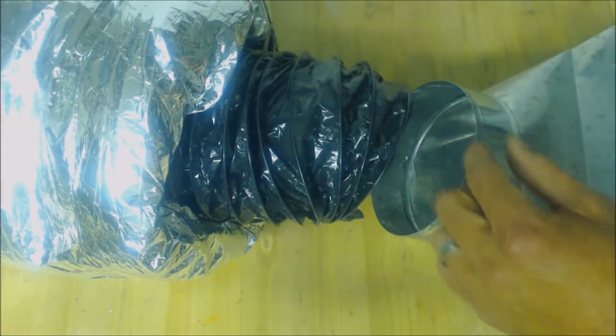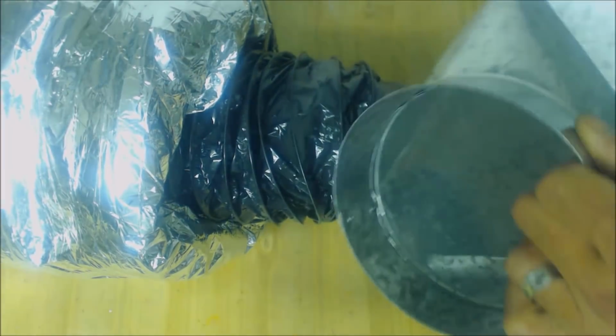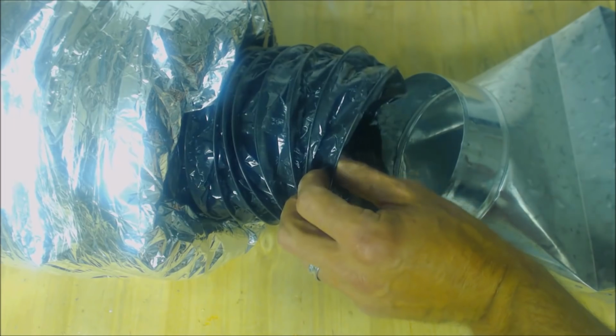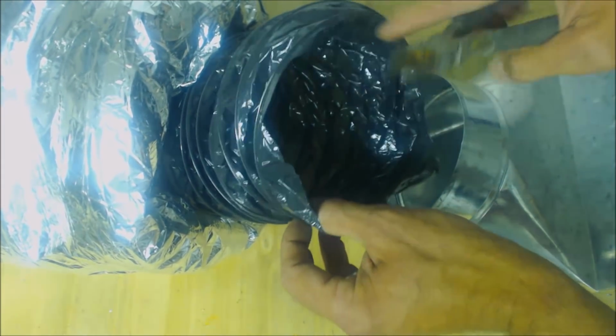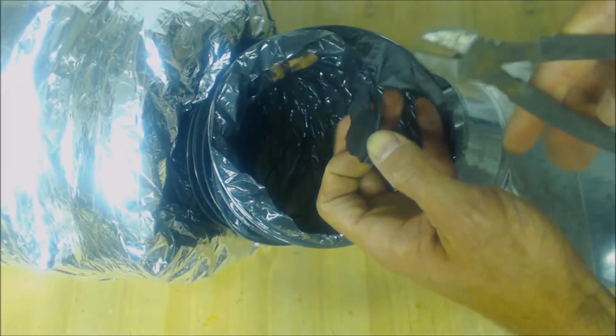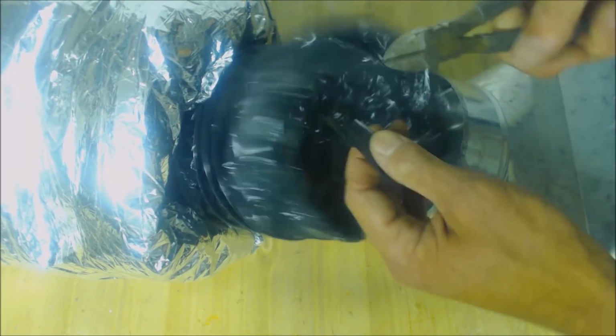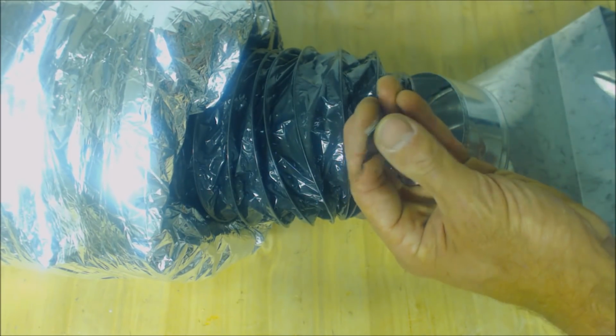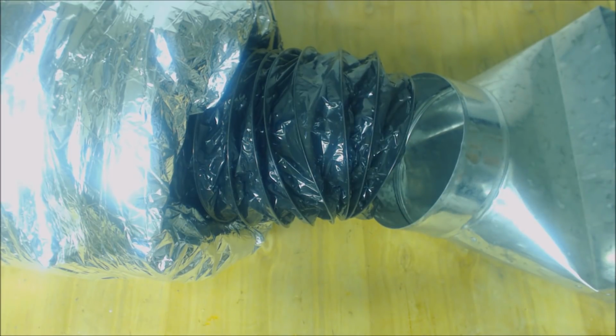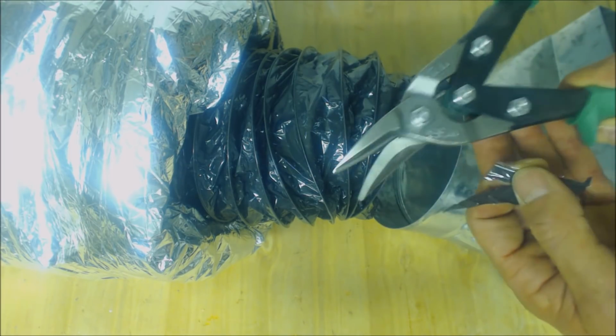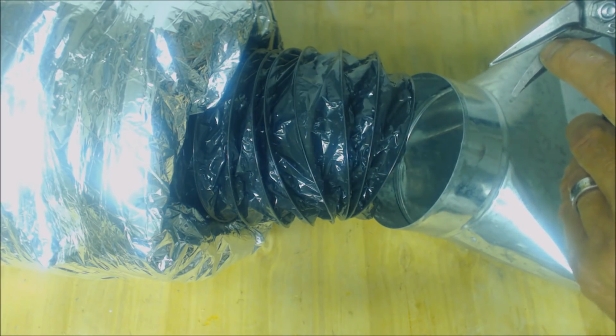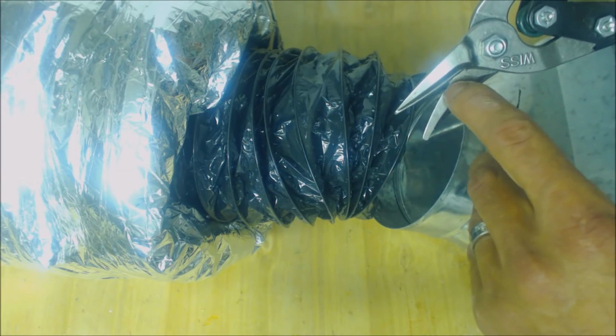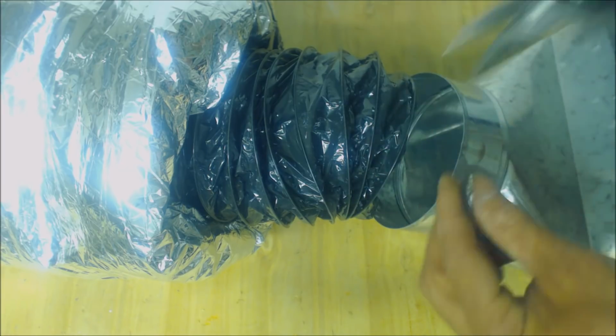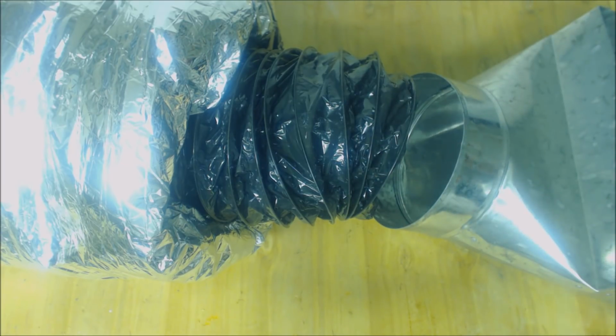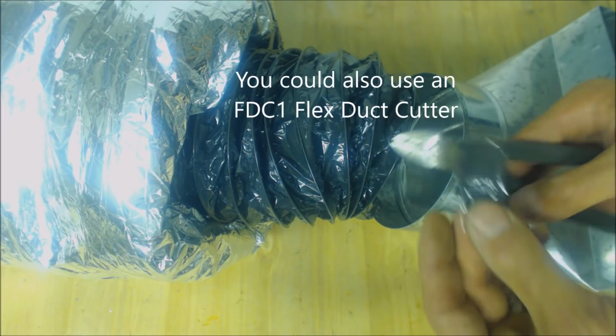Next we have connecting a flex into a boot. This is a 90-degree boot, 6-inch, and this is 6-inch flex. This inner wire right here, you want to cut with something like diagonal pliers, which are strong enough to cut that metal. Make sure you never use tin snips to try to cut it, because you'll break the tin snips, putting an indent in them that makes them no good to use afterward. Always use diagonal cutters or linesman pliers or something similar to cut it. Then you're going to use your strap tensioner, which has both a tensioning and a cutting feature.